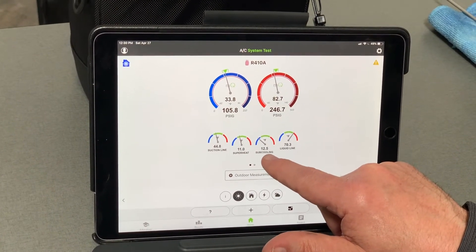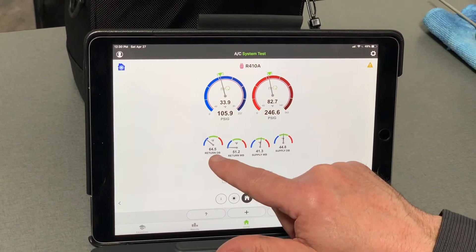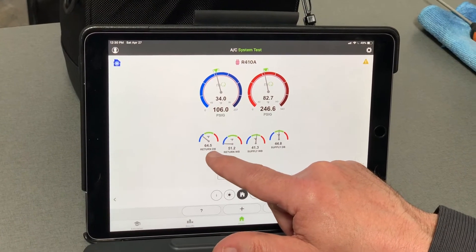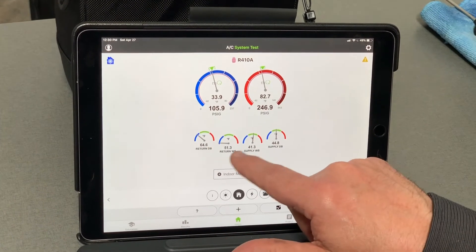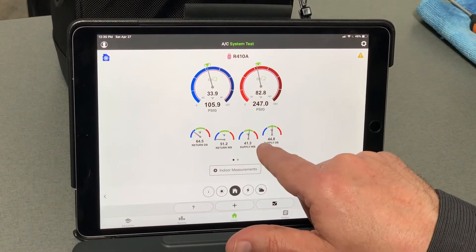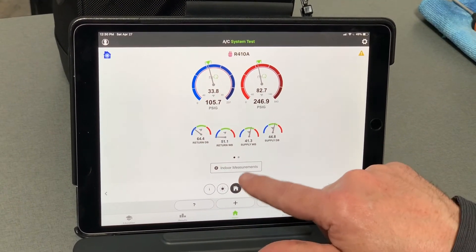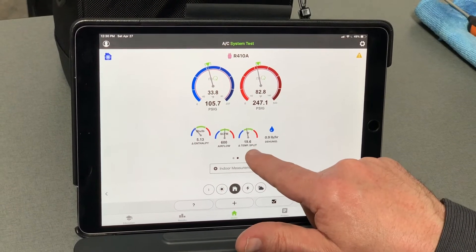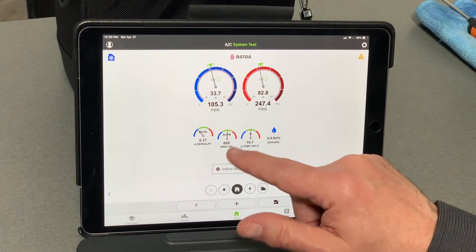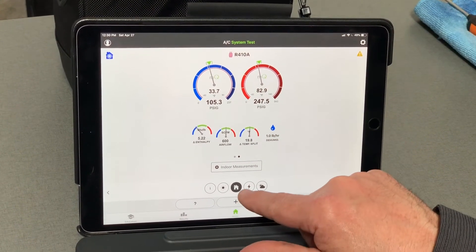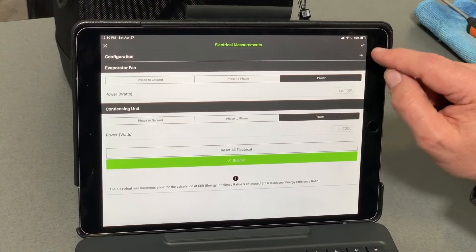In this case, superheat looks good, but our subcooling is a little low — we have a slight low charge situation from taking gauges on and off the machine all day. Return air dry bulb at 64 degrees is a bit cold. If I tap on any reading it shows how the system should be running. Our temperature split looks good — 64 to 44 is a 20-degree split; tapping again shows 19.6 degrees. Airflow looks good, split looks good, and all these targets are generated by that profile.